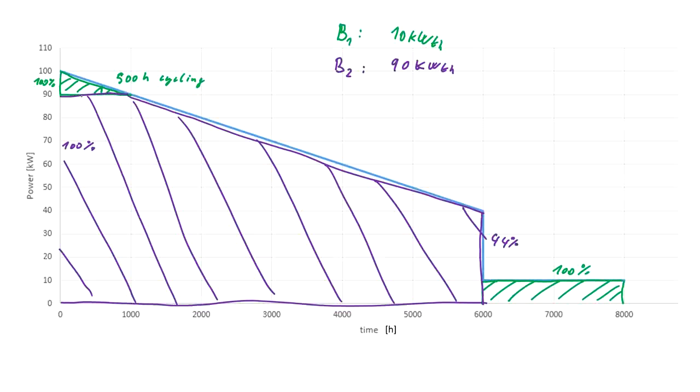determined, let's say for the green one, for the boiler 1, it's running 2000 hours at the full power, which is 10 kilowatts, plus 1000 hours times half of that on full power and then going to 0, so in average it's 50%.